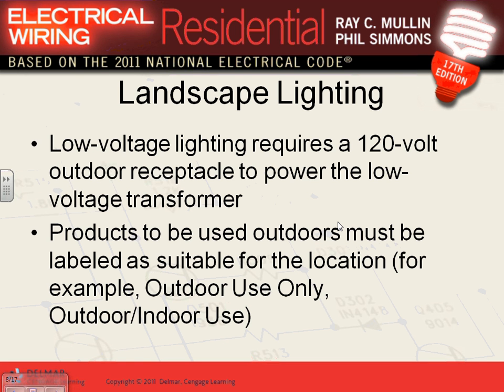Instead of bringing the hot and the neutral to two different locations on the light, he was tying the hot and neutral together. Now this is 24 volt, and tying them to one end, he's shorting them. But because they are 24 volt, they wouldn't trip the circuit breaker. Remember, they're 24 volt, you're shorting them, they wouldn't trip the circuit breaker fast enough to protect the transformer. So it keeps heating up, heating up, heating up until the transformer burns. But that's kind of his issue.